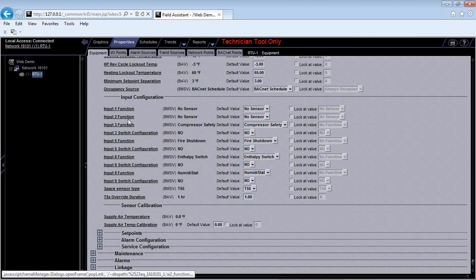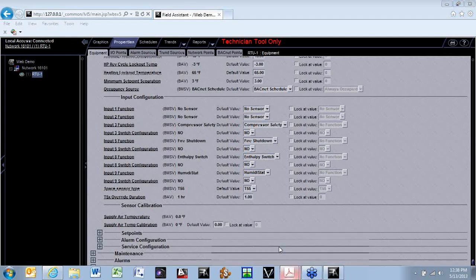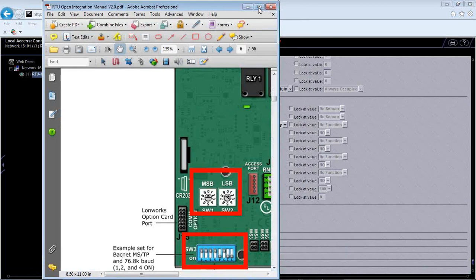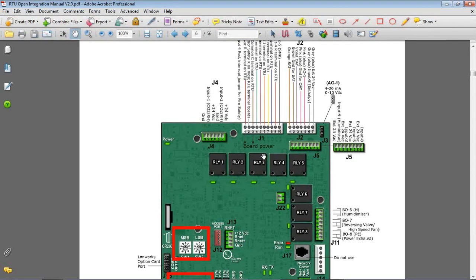And all of these inputs are what you're actually telling the controller what type of sensor you have wired in. Okay, so these inputs 1, 2, 3, 5, 8, and 9, you can actually see if I go back to my integration manual here, zoom out a bit, this will actually tell you the different input locations. Okay, so if I look on J5 over here, I have input 8, input 5, input 3, and input 9, all in this plug.